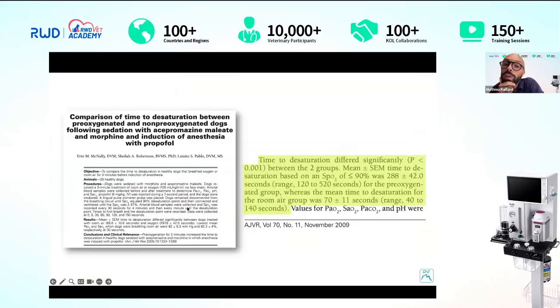So how much time are we talking about? If we prevent breathing, if we make an animal apneic and that animal was breathing room air, when it's a dog, it will desaturate in about 1 minute, 70 seconds. If I replace the nitrogen that was there by oxygen, 100% oxygen or something above 90% oxygen, and I prevent the animal from breathing, the animal will not desaturate before about 300 seconds, so 5 minutes.